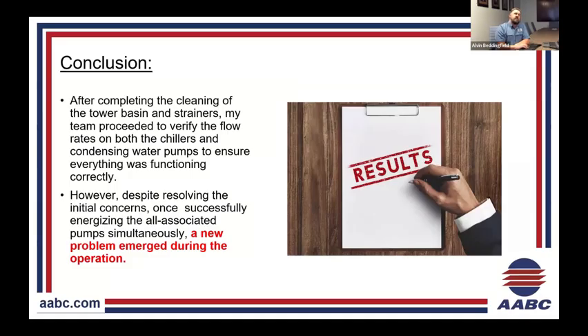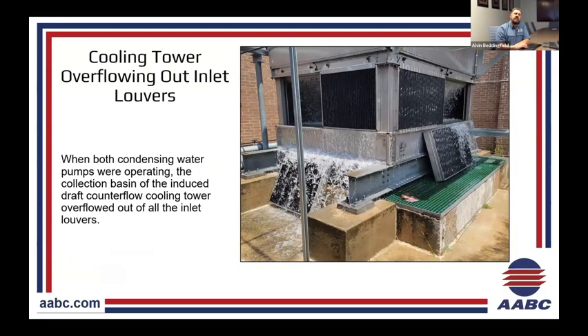So our conclusion after completing the tower basin was this: we took all the pressure measurements across the strainers, across the pumps, across the chillers, and realized that everything seems to be functioning and the chillers are maintaining. So we recontacted the chiller manufacturer. They came out and started up the chillers, no problem. Once we started up one chiller, no issues, everything was working. We decided to run both pieces of equipment just to make sure there were no other restrictions, and we came across the next problem, which we had to address.